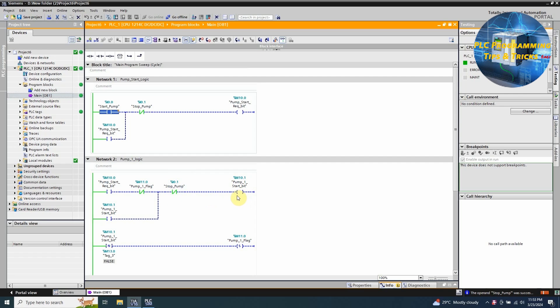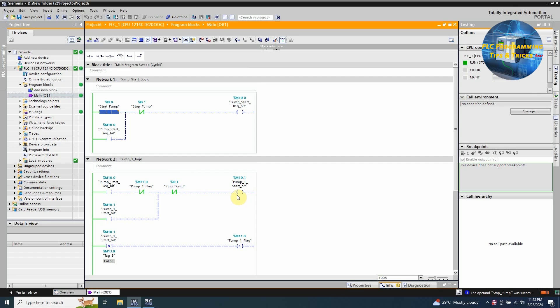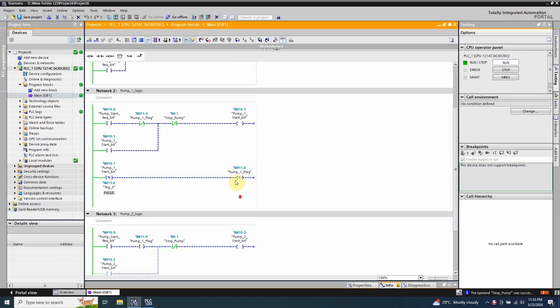If we press the stop pump button I0.1, this will latch off the pump 1 start bit M10.1. Now as soon as this bit turns off, on the negative edge of this bit, it will set on the bit M11.0. This bit will turn on and indicate that pump 1 turned on last time.